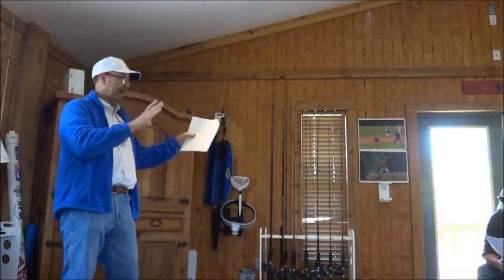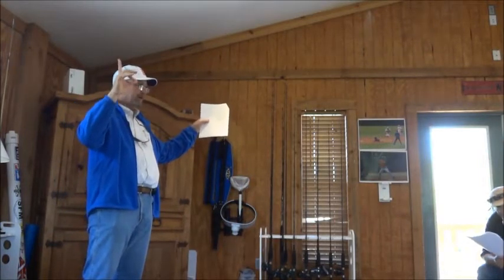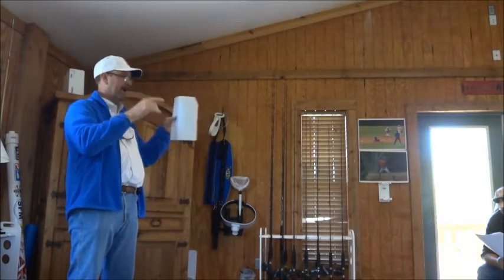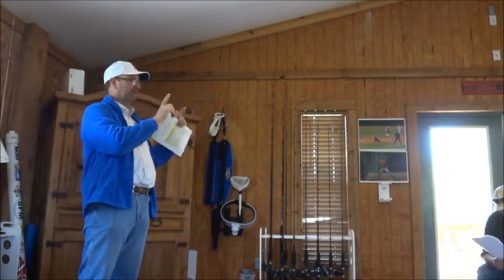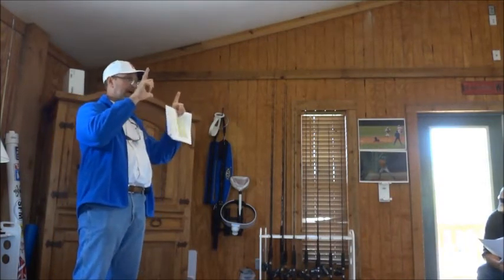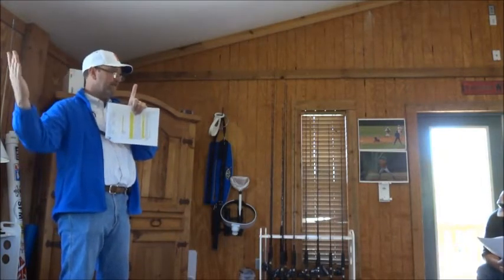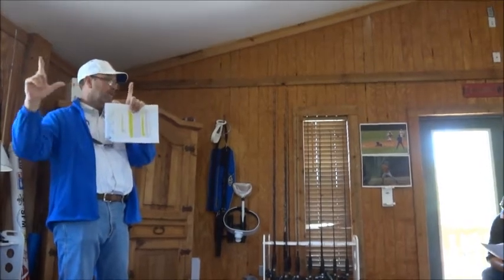They then look at that, add up the 12, look at it for a year, divide it by the 365 of sorts, and then see what that value is, and compare it to your permit. Now they do that every month, so it becomes a moving annual average that moves through time. Each time you add a month, one drops off, so that it is a moving window of pumpage.